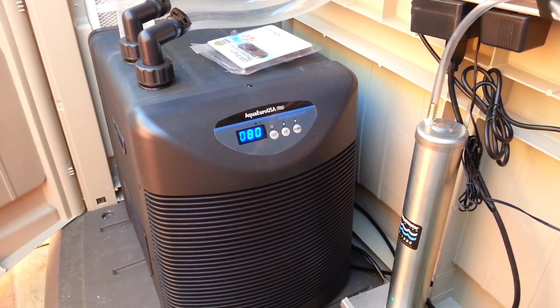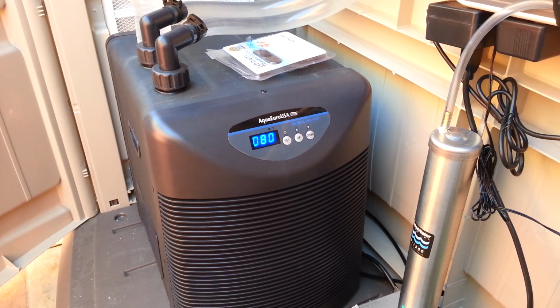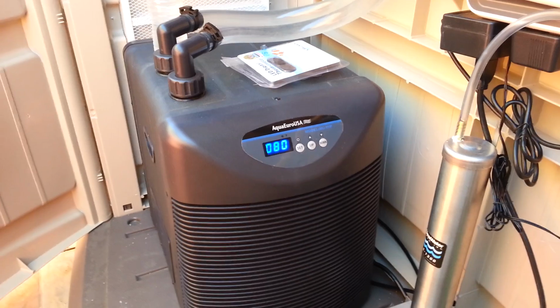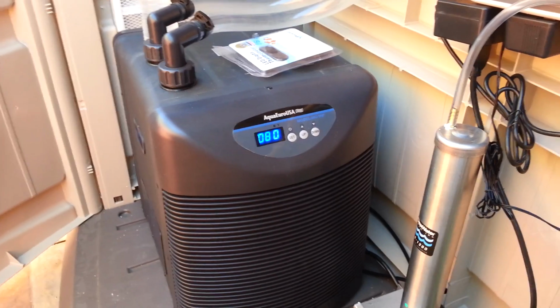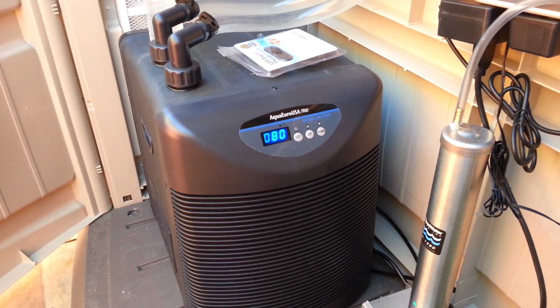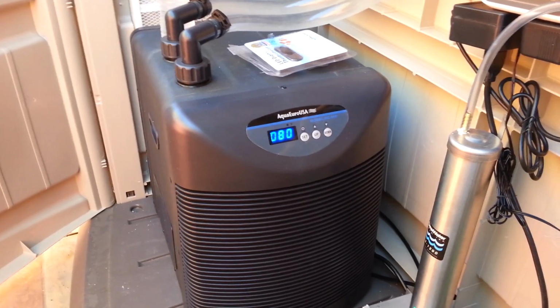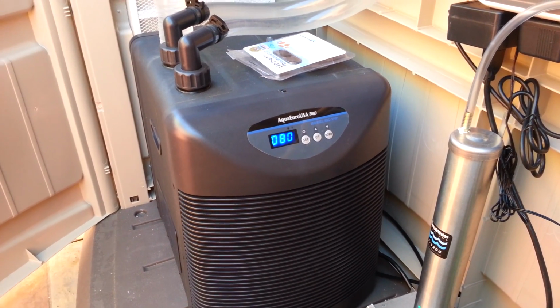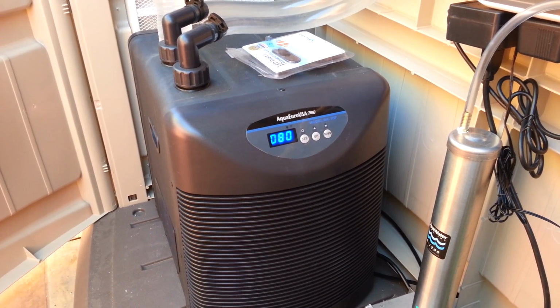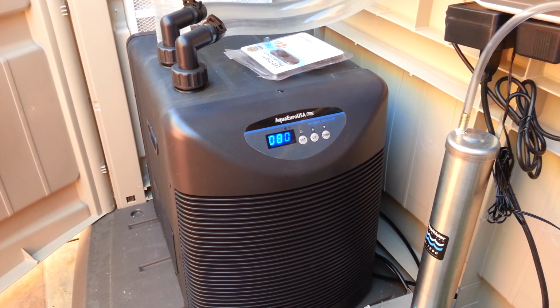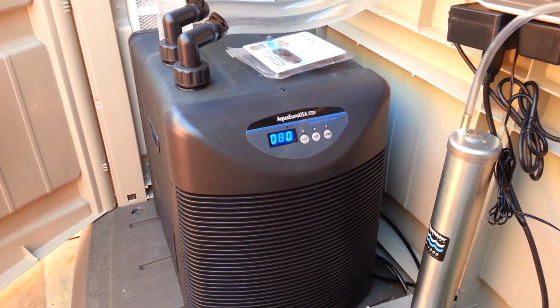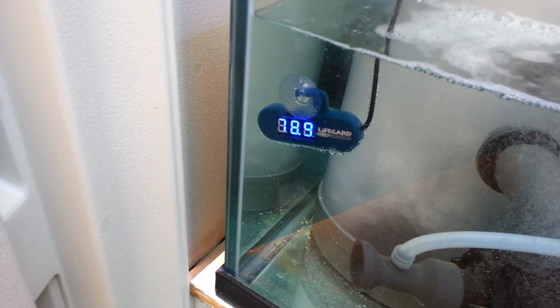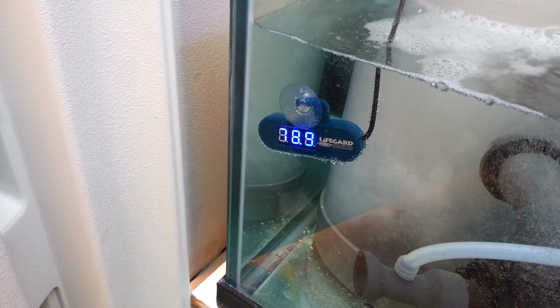So nothing's changed, nothing got added to the heat load of the system. No lights came on, no extra pumps turned on. Everything is the same as it was before the chiller just started up a minute ago, and it's reading higher than it was, which really makes no sense at all. Now, it's only been running for a couple of minutes. I wouldn't expect that to change right there, but it's about the same. It only just kicked on.